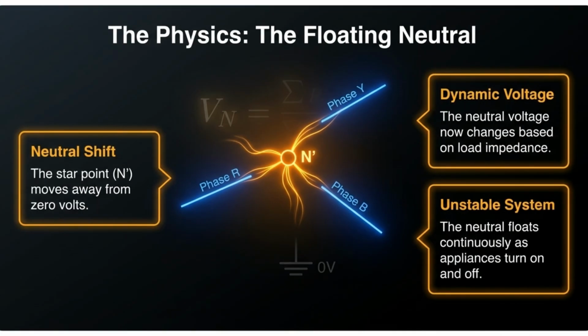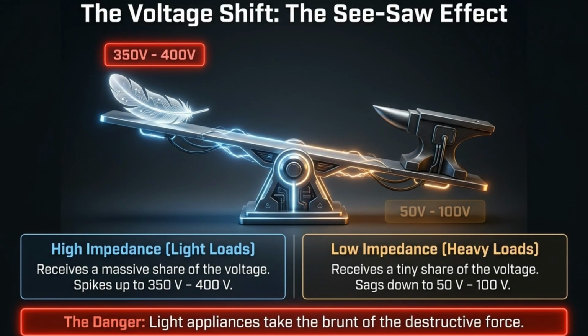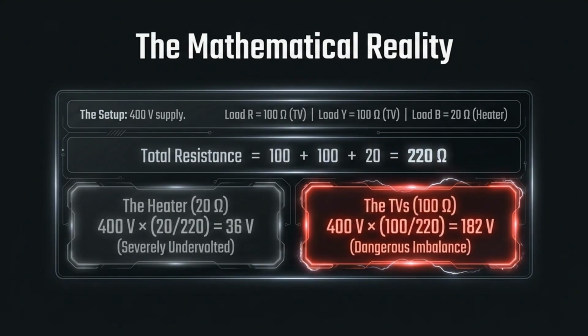This results in a floating neutral. The star point of the system shifts away from 0 volts, creating a dynamic and unstable environment where voltages fluctuate based on your connected loads. Think of it like a seesaw. Light loads with high impedance can suddenly experience dangerous voltage spikes, while heavy loads may see their voltage sag significantly. Mathematically, this leads to an imbalance. A heater with low resistance might be severely undervolted, while sensitive devices like televisions may receive a dangerously high voltage.